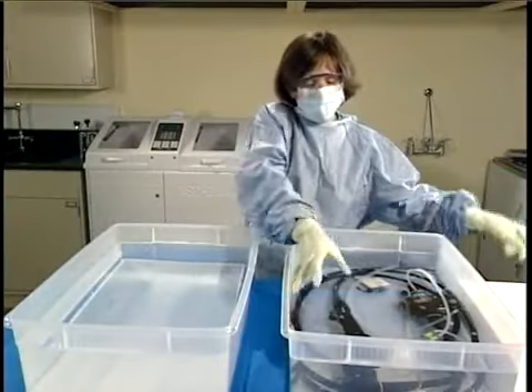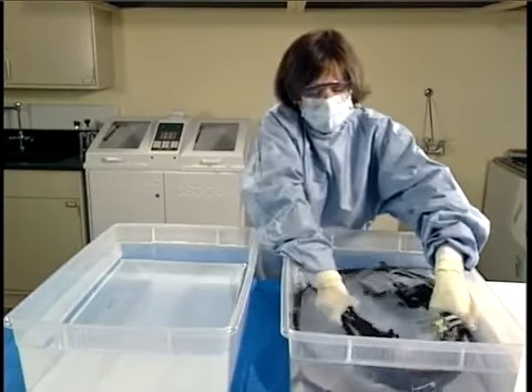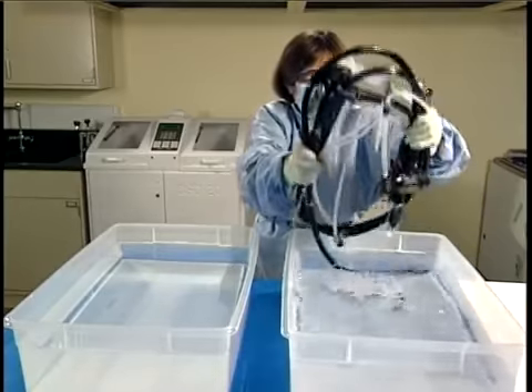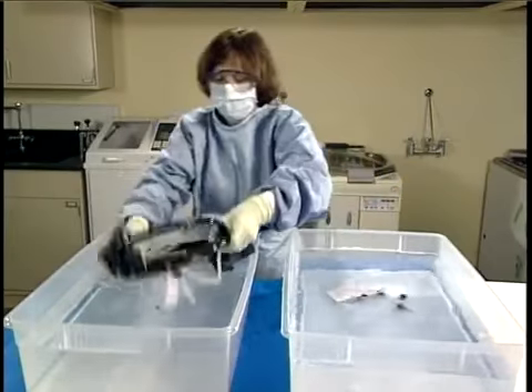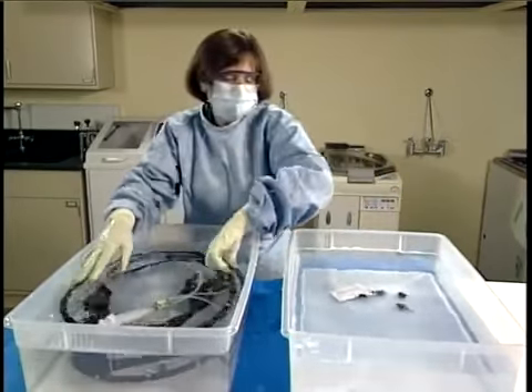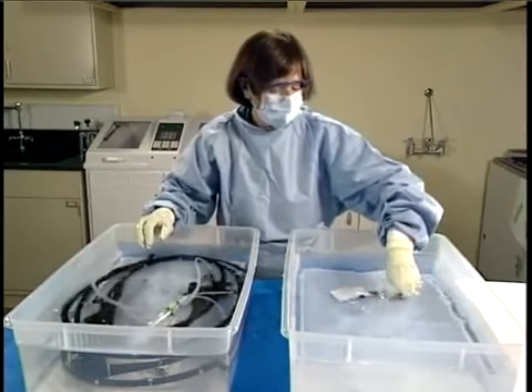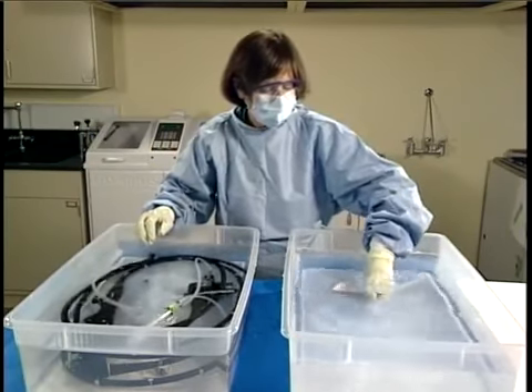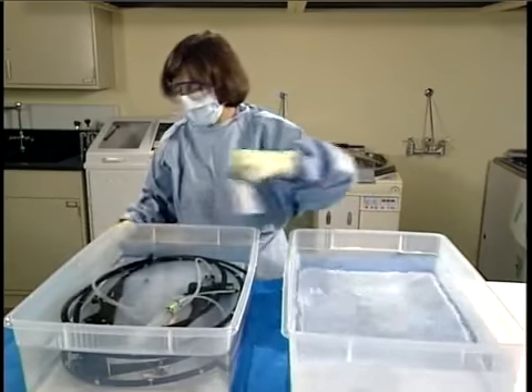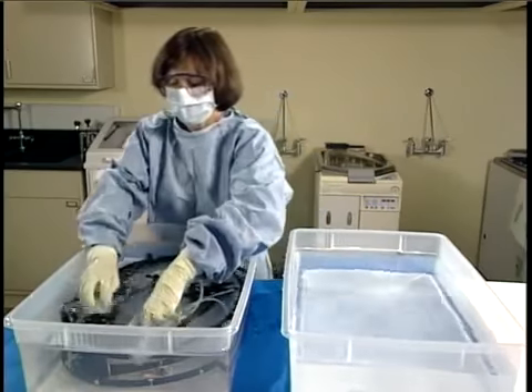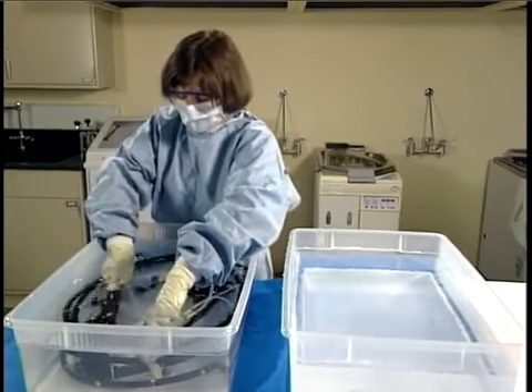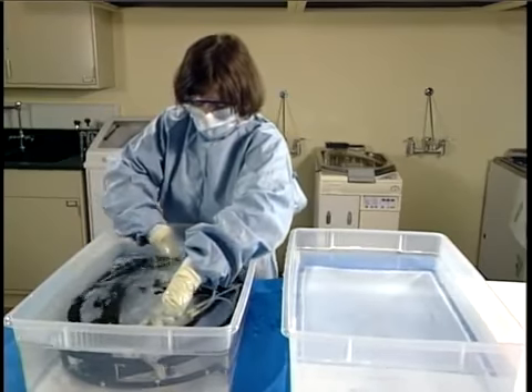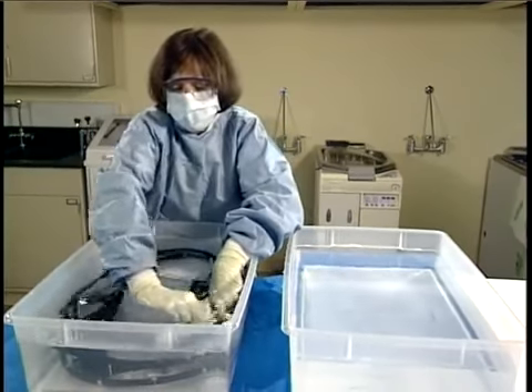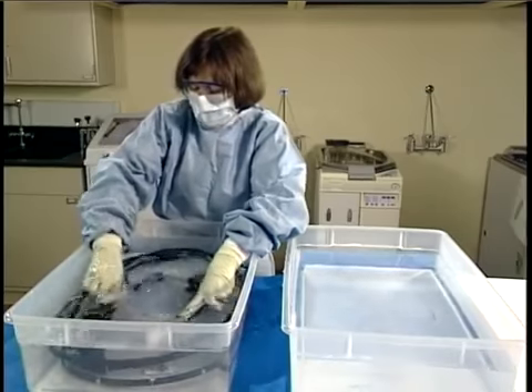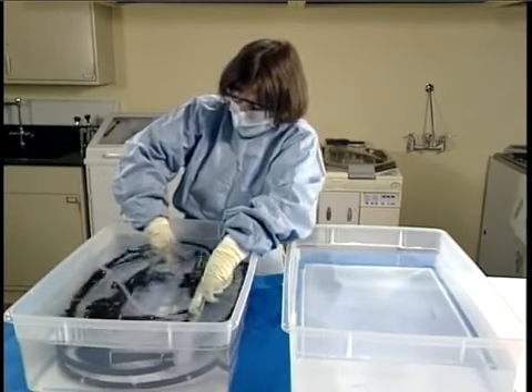The next step is to rinse the detergent from the endoscope. It is critical to remove all traces of detergent, as it may interact with or inhibit the activity of the high-level disinfectant or sterilant. Transfer the endoscope and accessories to a basin or sink filled with clean water. Wipe all external surfaces of the equipment with a clean cloth.